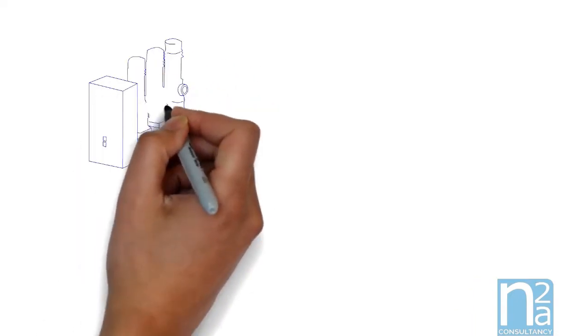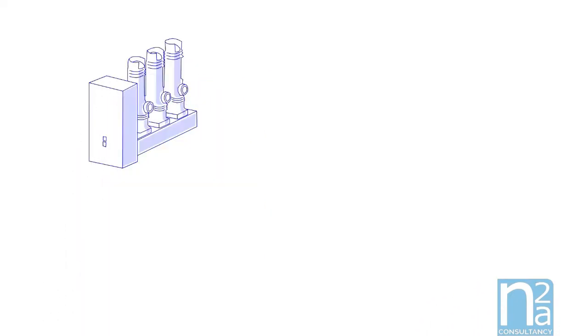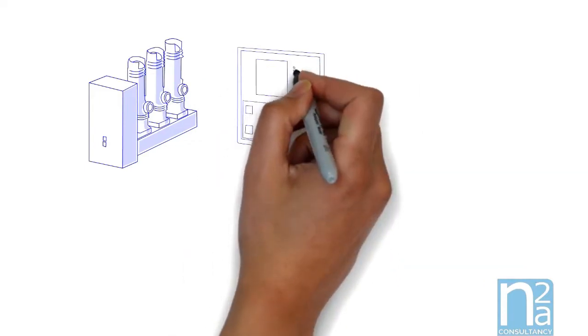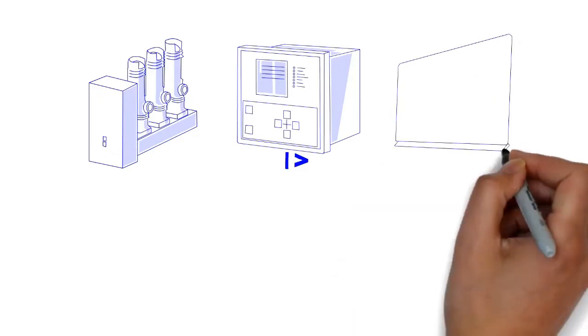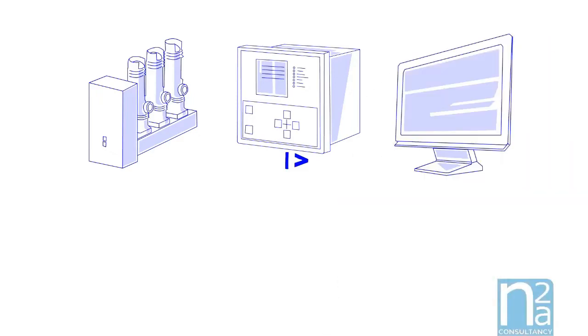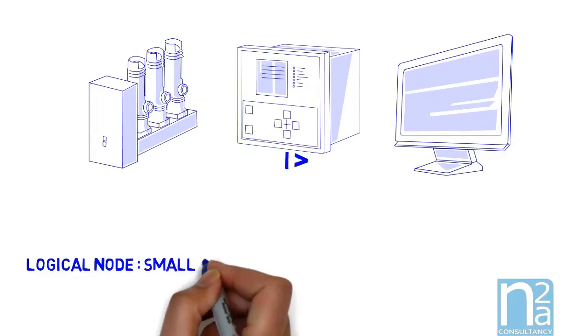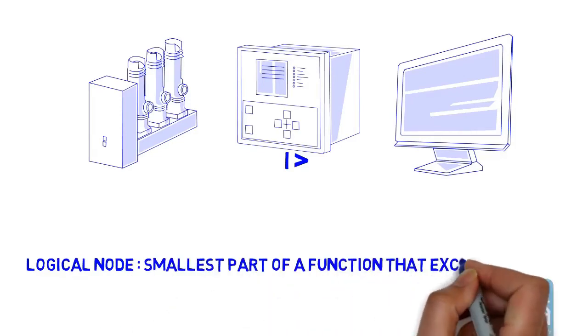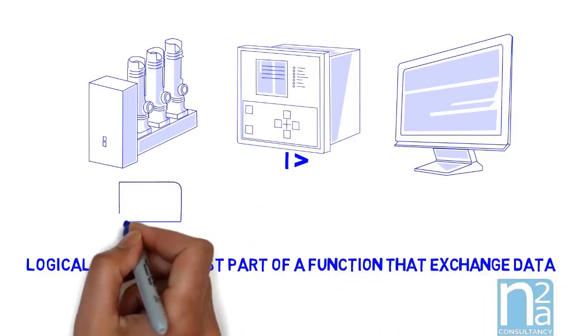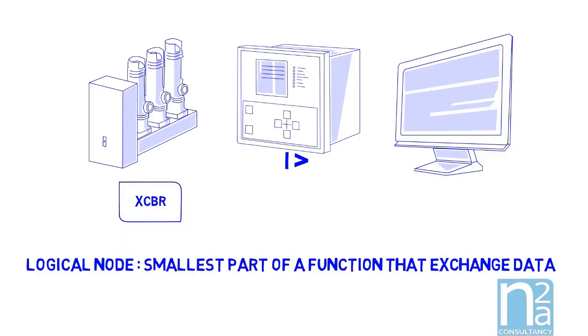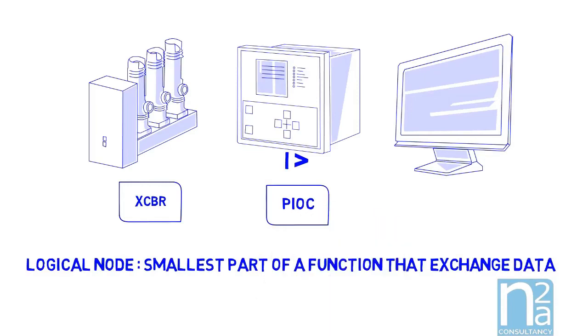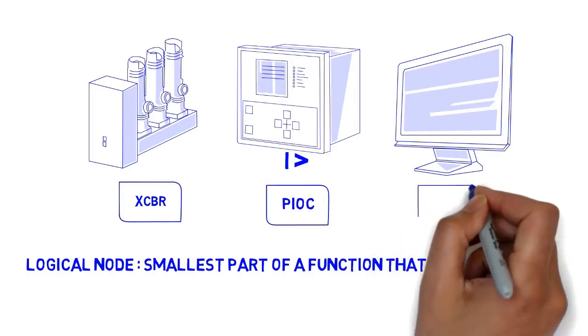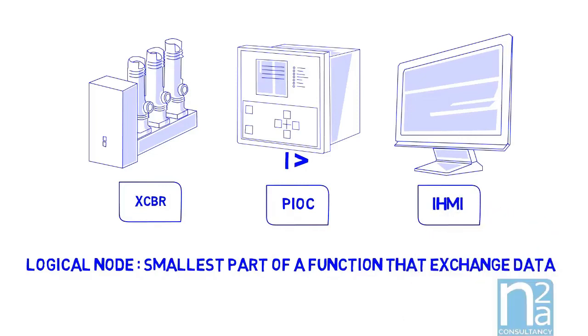Now we had described the communication process, we need to define the structure of the information. IEC 61850 has modeled all devices and functions in a switchgear with an object-oriented description. The key element of this modelization is the logical node. A logical node represents the smallest part of a function that exchanges data with a predefined name, from a device from the process level like a circuit breaker XCBR, or a logical function from the bay level like an instantaneous over-current protection PIOC, or a function from the station level like the HMI called IHMI.